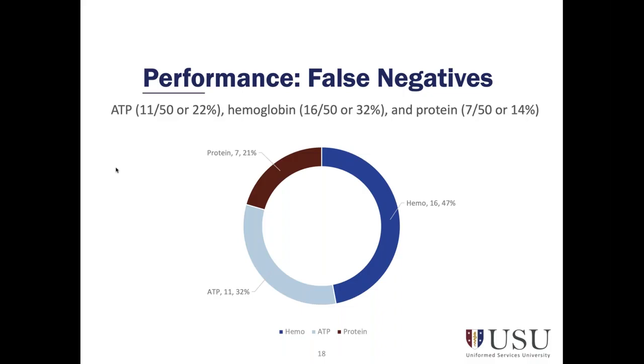Now, this was not a surprise. This is nothing that the manufacturer is not already telling you. In the case of ATP, if you are testing an instrument that has been improperly cleaned and has been through multiple sterilization cycles, you cannot expect to detect anything living on that instrument. If you swab it and get something back, you're trying to test for inorganic material, which in the case of ATP is not going to work, because you need ATP, and that's energy coming from some sort of living cell. The same could happen to protein if the protein has denatured to the point that it's not detectable anymore.